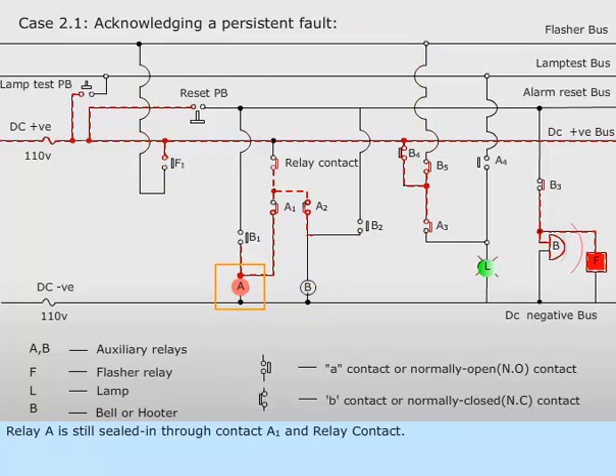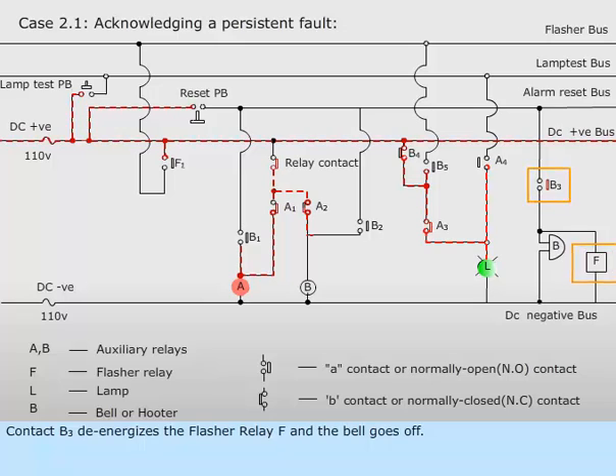Relay A is still sealed in through contact A sub 1 and relay contact. Contact B sub 2 opens the sealed in circuit of relay B. Contact B sub 3 de-energizes the flasher relay F and the bell goes off.